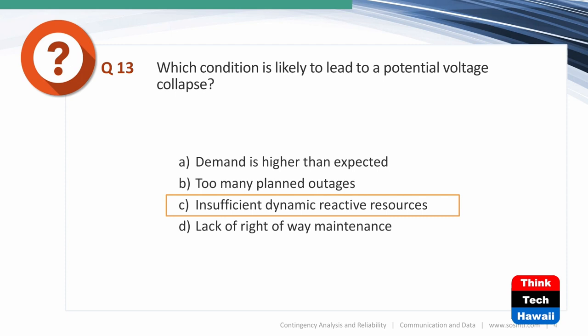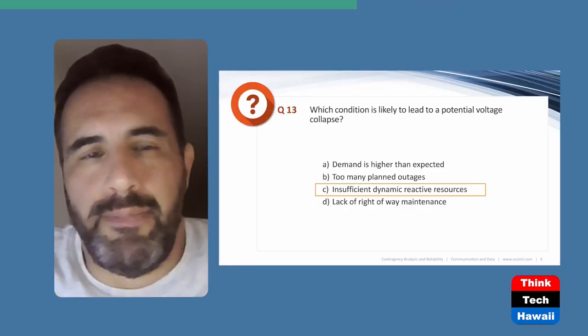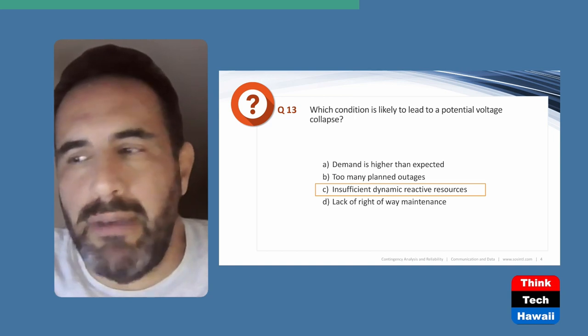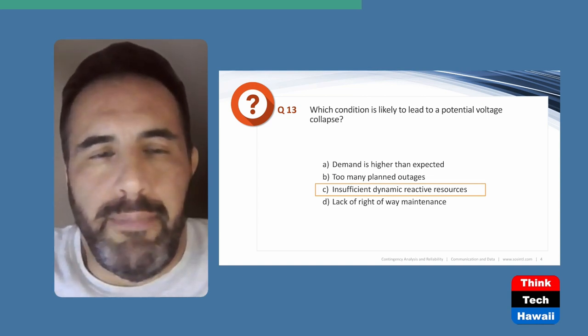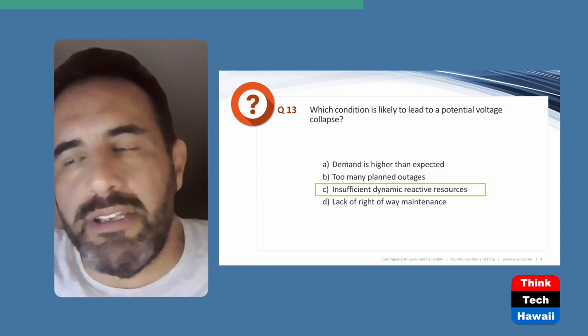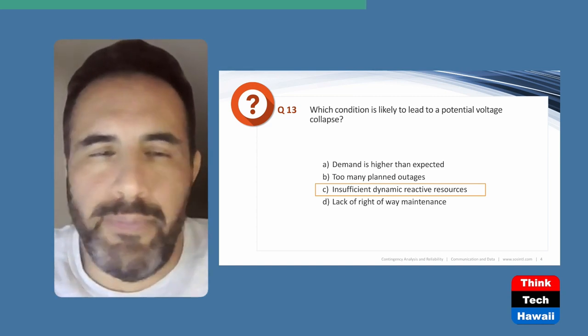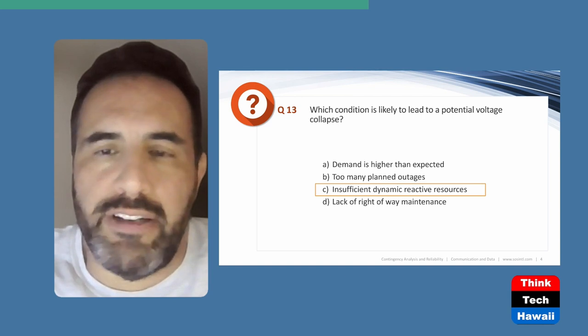Next question: Which condition is likely to lead to a potential voltage collapse? The answer is insufficient dynamic reactive resources. Let's talk about why the others are wrong. Demand higher than expected can be a component, but usually many more things have to go wrong for a voltage collapse. Too many planned outages could also contribute, but it's not the primary cause. Lack of right-of-way maintenance would more likely lead to a line fault, not a voltage collapse.